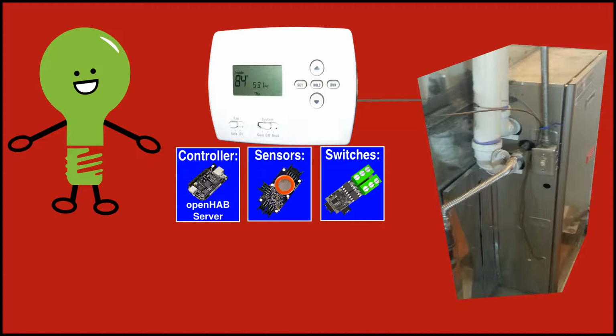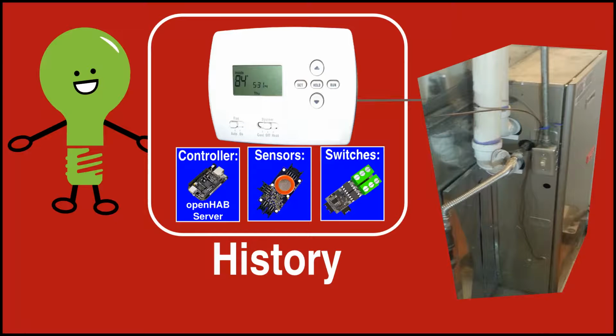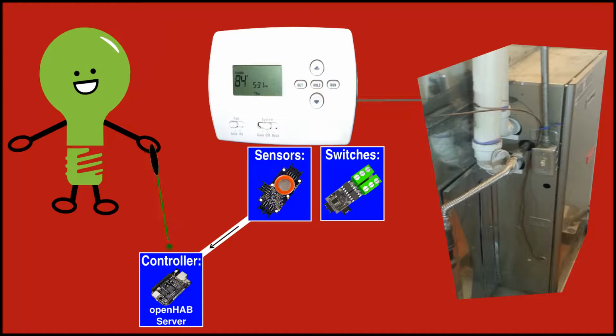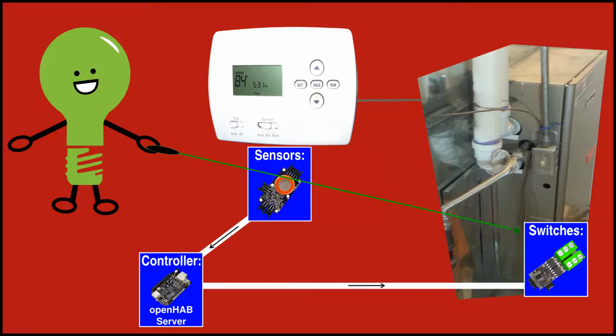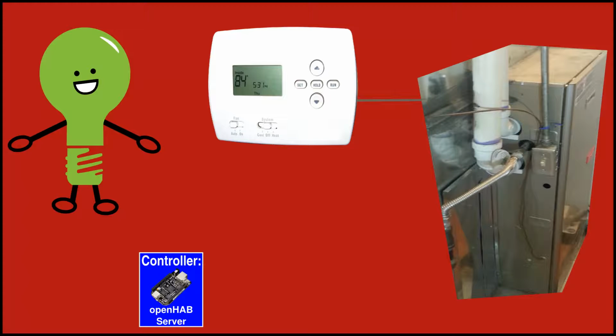Traditionally, thermostats have included the controller, sensor, and switches in an enclosure that would be put in a central point in the living space. With our system, the controller will be an OpenHAB server to allow us to control the thermostat from our computer, tablet, or smartphone. Generally, we will use one OpenHAB server for all our home automation needs, so it will likely not be in the thermostat enclosure. The switches do not have to be in the thermostat enclosure either. Depending on a home's layout, it may make sense for the switches to be at the HVAC system. As long as the sensors can report conditions to the OpenHAB server, you can put one or more of them wherever you wish. This flexibility may make it easier for you to install your system.